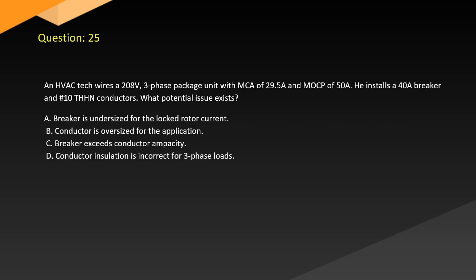Question 25. An HVAC tech wires a 208-volt three-phase package unit with an MCA of 29.5 and an MOP of 50. He installs a 40-amp breaker and number 10 THHN conductors. What potential issue exists? A. Breaker is undersized for the locked rotor current. B. Conductor is oversized for the application. C. Breaker exceeds conductor ampacity. D. Conductor insulation is incorrect for three-phase loads.